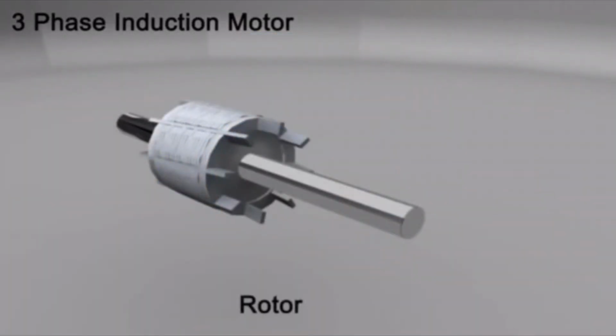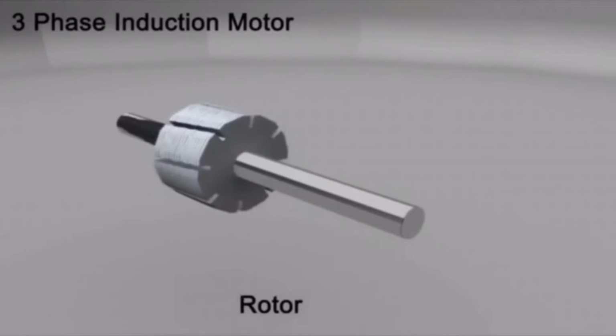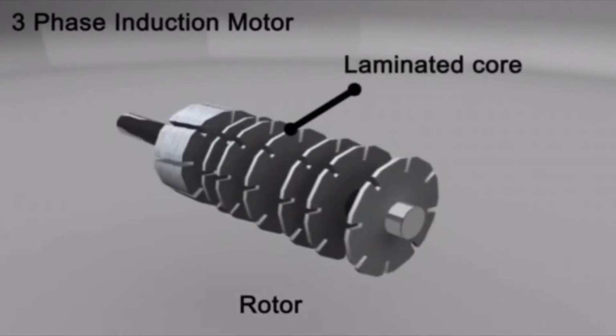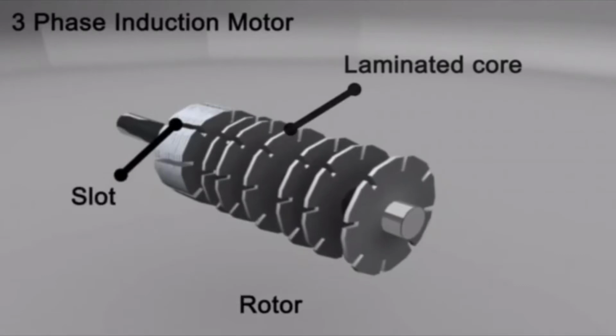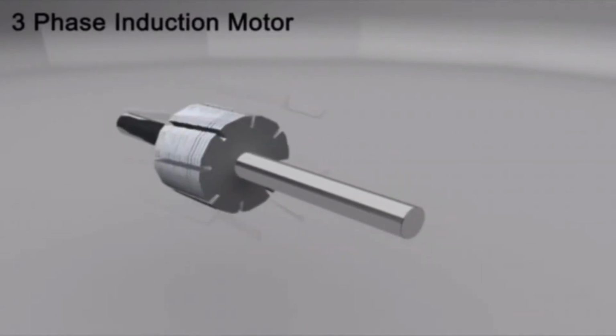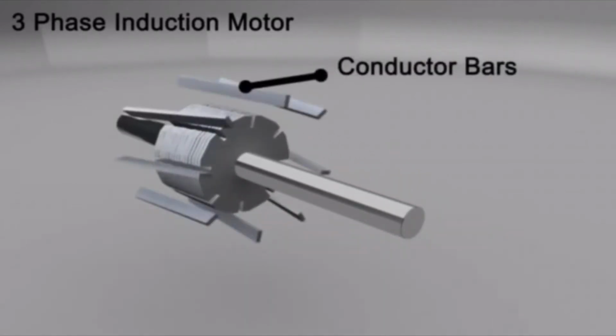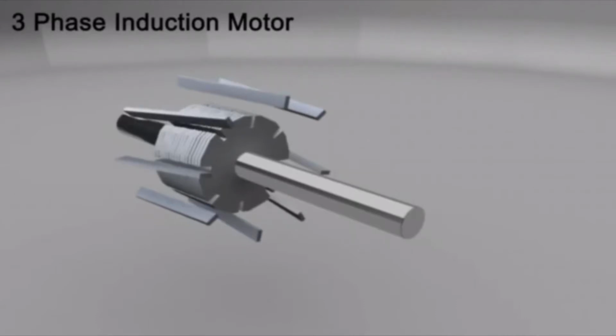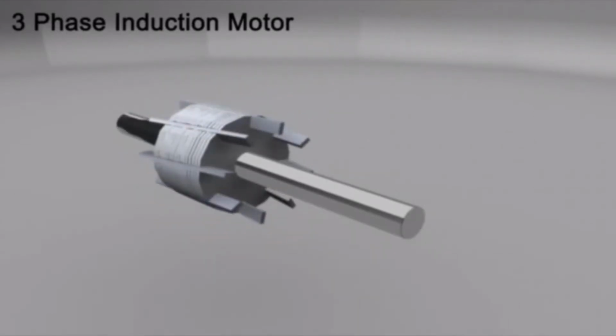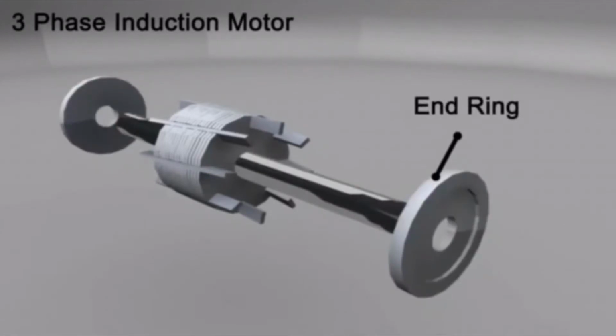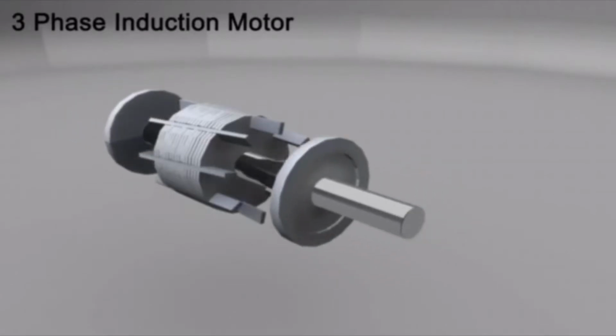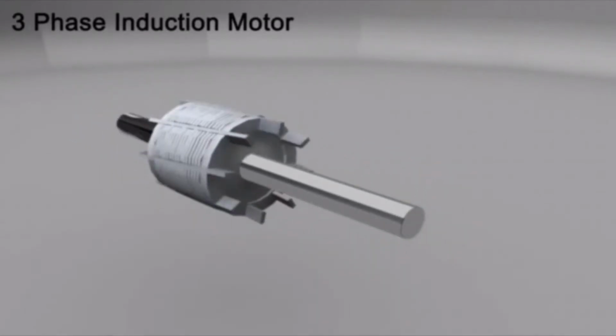Rotor. The rotor consists of a cylindrical laminated core with parallel slots that carry conductor bars. Conductors are heavy copper or aluminum bars which fit in each slot. These conductors are brazed to the short-circuiting end ring. The slots are not exactly parallel to the axis of the shaft but are slotted a little skewed for the following reason.